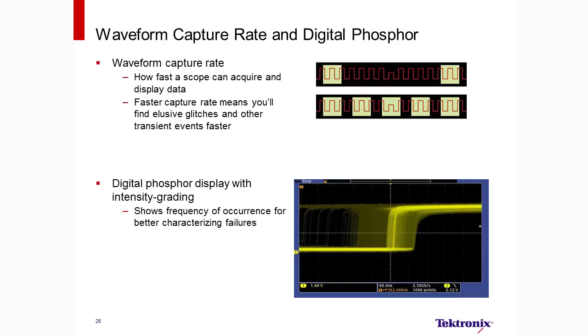Now, in addition to being able to capture the waveforms, the instrument needs to be able to display the information in a way that makes sense. Just because the scope can capture thousands of waveforms per second doesn't mean our eye can see them all. So some scopes have the ability to use intensity grading to represent how often an event occurs. Infrequent events appear dim and frequent events appear brighter. Because it looks like the phosphor on an analog CRT, Tektronix calls this function digital phosphor. And you'll find it on Tektronix scopes from basic bench models to high-performance lab instruments. The lower picture on the slide shows how a digital signal varies in time relative to the trigger, which is off the left-hand side of the screen. You can see by the intensity that the rising edge spends most of its time in the center of the screen, but moves over about four divisions. And occasionally the edge happens even sooner.